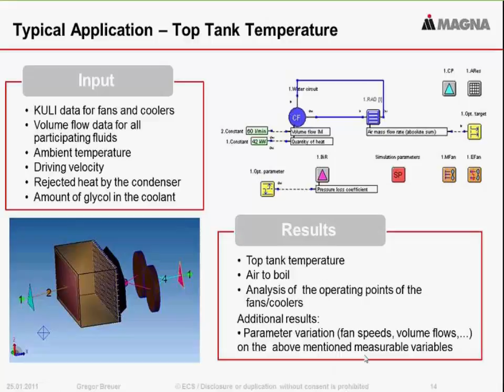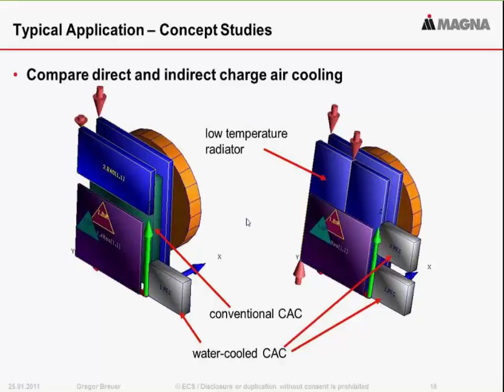An additional application is making concept studies. For example, what happens if I use a conventional charge air cooler versus a water-cooled charge air cooler in this application. You can build up this system quickly—setup normally takes a few minutes, and steady-state calculations take only parts of seconds to get results. Then you can see what you can do: arrange the components in line or side by side, use one high temperature radiator and one low temperature radiator, use water-cooled charge air coolers, and make many variants in a short time. At the end, you have one solution that fulfills your targets, and you build the prototype based on it, which normally fits your targets.